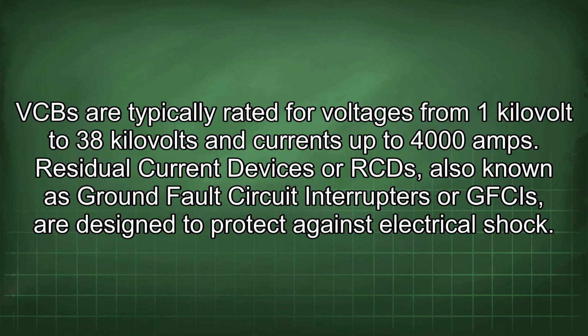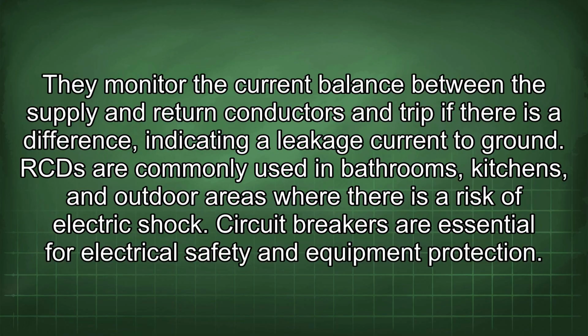Residual current devices, or RCDs, also known as ground fault circuit interrupters or GFCIs, are designed to protect against electrical shock. They monitor the current balance between the supply and return conductors and trip if there is a difference, indicating a leakage current to ground. RCDs are commonly used in bathrooms, kitchens, and outdoor areas where there is a risk of electric shock.